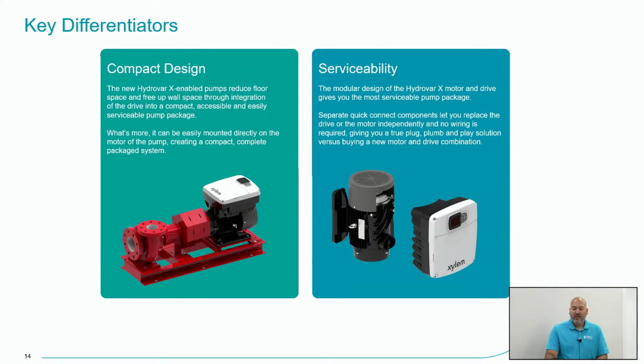And not only that, by taking the VFD off of the motor, there is still no unwiring or rewiring required from the customer. There is a quick connection port between the motor and the VFD. So you're simply unscrewing a few screws on the side of the VFD, and you can pull off that VFD plug there. So it's even quick and simple to do some replacement or serviceability on the product.